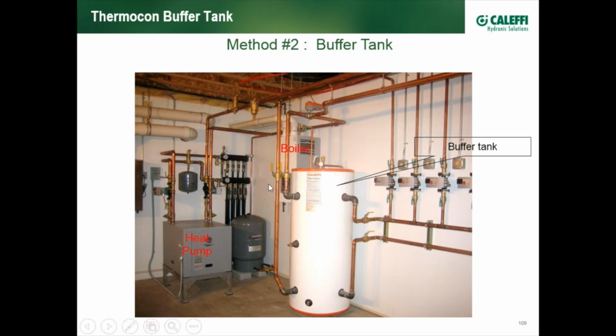The secondary is separated from the primary over here. The Caleffi buffer tank has multiple ports allowing multiple heat generators to be connected to it. These pumps don't see each other, and the pumps driving the boiler and the pump driving the heat pump don't even know one another exists. Okay, now why a buffer tank rather than closely spaced T's? Well, this system is highly zoned. There are some zones, heating zones, that have a load very small in relationship to the capacity of the boiler, the smallest turndown capacity of the boiler or the heat pump.